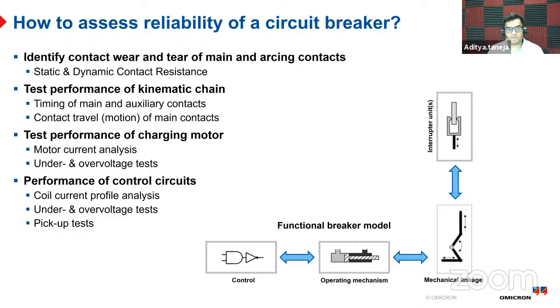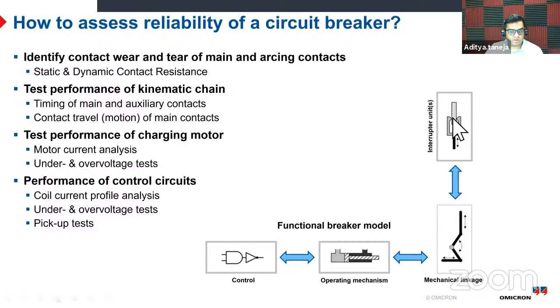And this is not enough, actually. This is only a part of electrical test. Then you have some insulating features also of the breaker, that is insulating between contacts and ground and between the contacts. The standard says you have to do an AC high voltage test. But normally people do a DC high voltage test, and they do the insulation resistance between the contacts, between contact and ground, and between phases. But that is also okay. Then check the health of the insulating media, SF6 density, and all these things. So there are some more tests on the insulation which you can do in addition to this.